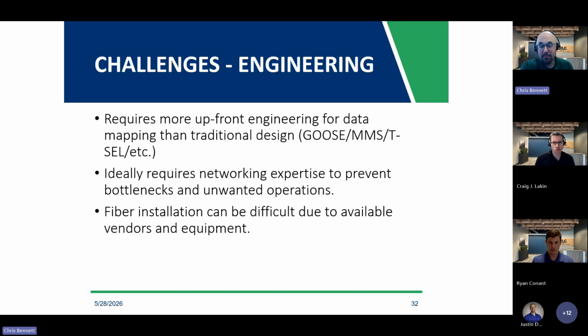And finally, the engineering challenges that come along with 61850 and these all-digital centralized protection and control designs: it will require more upfront engineering for data mapping. You need to set up your GOOSE and MMS subscriber network, and even with SEL, you need to make sure that you are connecting the data streams correctly. I will use data streams as a generalized term. Also on top of this, the P&C engineers and the design engineers will likely need some kind of networking experience to account for all these changes with fibers and SFP ports and Ethernet ports and Ethernet switches and what's best for my design.